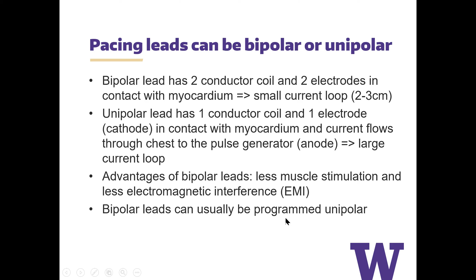So here are the 2 types of bipolar lead conductors that exist. Most commonly nowadays is the coaxial system. Again, 2 electrodes, 2 wires going coaxially, so one looping around the other. The advantage of this is that each is insulated separately, so that if you have a break in the insulation of the outer sheath, this wire might be jeopardized, but you can still program the device unipolar by using just the cathode tip. And so that makes this advantageous.